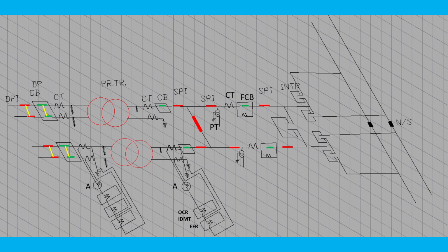Fault current also it can be closed or opened, but it will open immediately through the relay operation. And this interrupter, which is used on the feeding side to feed the OHE, can also be closed or opened from no load to full load, even in faulty condition, but it cannot open automatically, except in the SP neutral section.